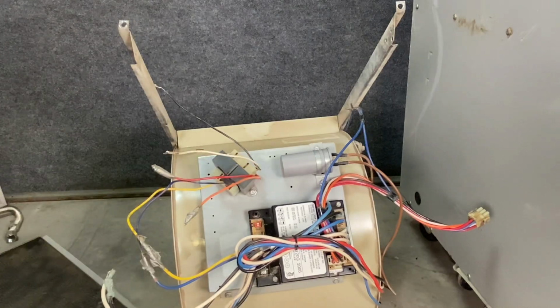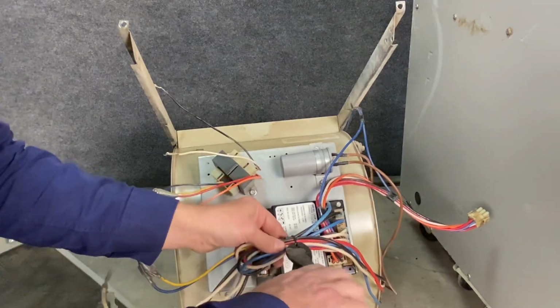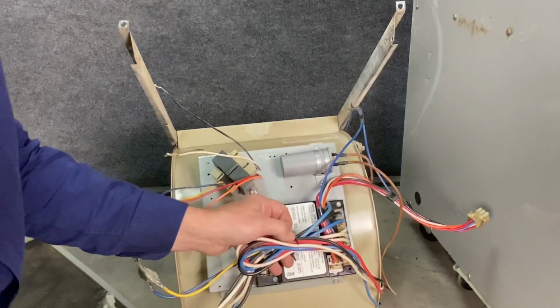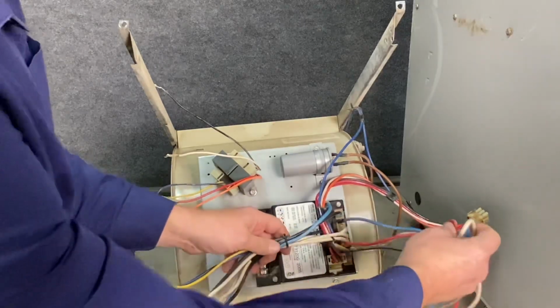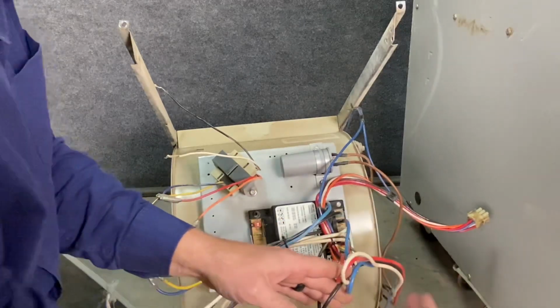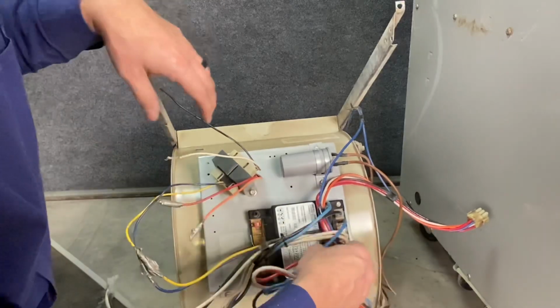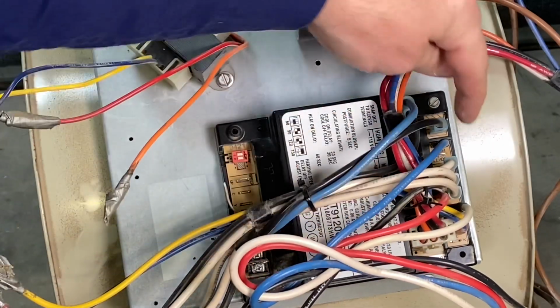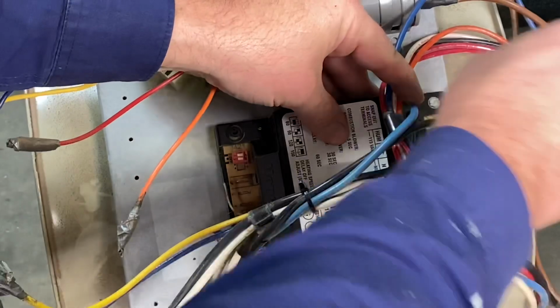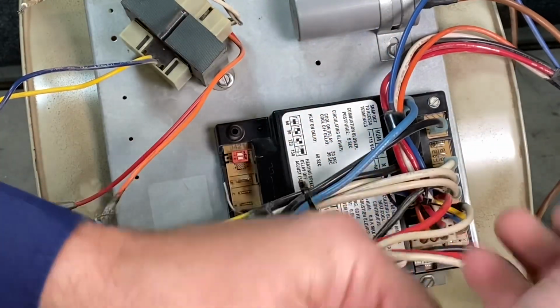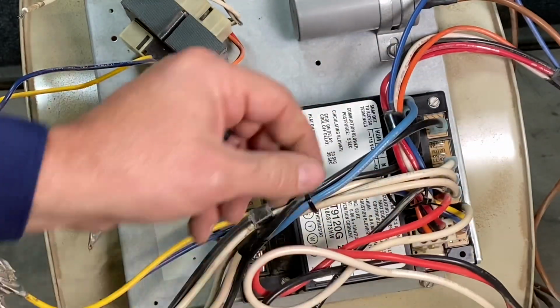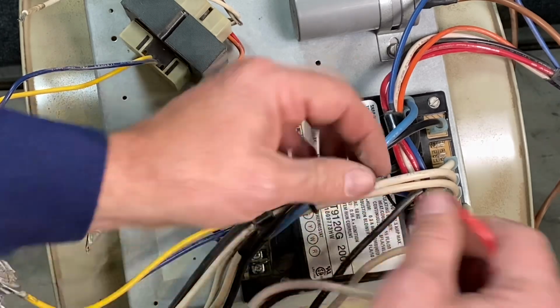So we're going to cut the cable tie off of these units so we can see this wiring better. Just going to take and cut that off. And here, these are going to be the wires going to the motor, just for the blower motor. Here we can see this blue wire is on a tap called unused. That means this speed of the motor is not being used at all. Now we look at another wire. We have here the red wire.